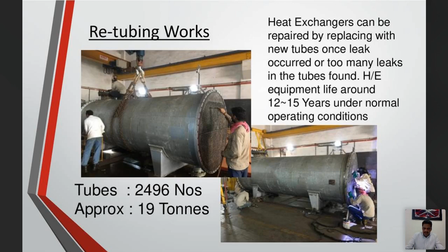Yes, we can recondition it, because you don't need to throw it. For example, here you see 19 tons, people don't want to throw it. So what we do is remove the existing old tubes, put in new tubes, and put it back into service. Instead of 12 to 15 years, the service will be enhanced for another 5 to 6 years.